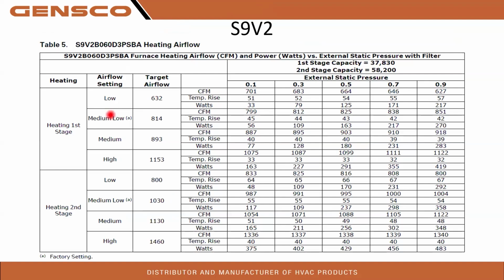S9V2, again, here's our 2-stage. We have a Medium Low 814. If we have the 0.5, let's go to 0.7 static, we're going to be producing 838 CFM. We should have about a 42-degree rise. High side, where you're looking at about 1,000 CFM. Again, we can change these speed taps on the fly through the board.